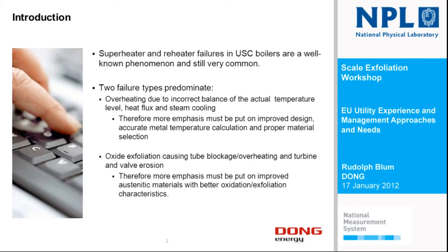We began to utilize austenitic material in the beginning of the 90s because we elevated steam parameters, and we exceeded the 540 centigrades, which was a limit for only using ferritic materials, and going to 560 first and then later to 600 centigrades, we had to use austenitic materials.